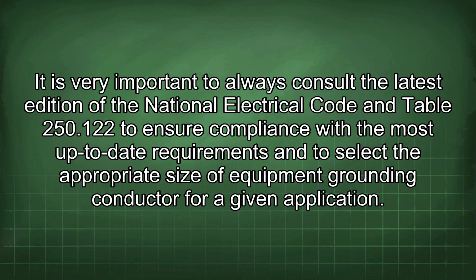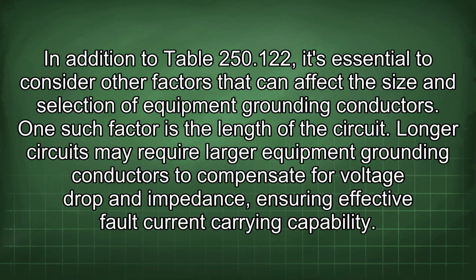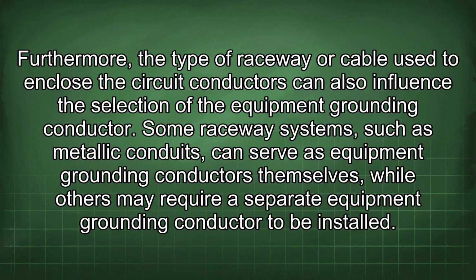In addition to Table 250.122, it's essential to consider other factors that can affect the size and selection of equipment grounding conductors. One such factor is the length of the circuit. Longer circuits may require larger equipment grounding conductors to compensate for voltage drop and impedance, ensuring effective fault current carrying capability. Furthermore, the type of raceway or cable used to enclose the circuit conductors can also influence the selection of the equipment grounding conductor. Some raceway systems, such as metallic conduits, can serve as equipment grounding conductors themselves, while others may require a separate equipment grounding conductor to be installed.